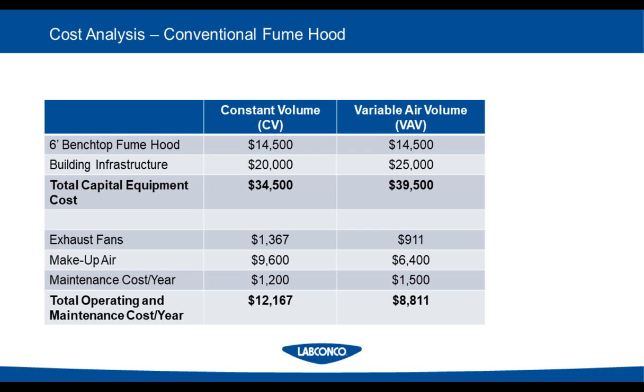And again, drawing attention to the makeup air portion of this table, it only requires about $6,400. And this number comes from taking a typical cost for fume hoods of about $8 per CFM per year. And that's where we're getting these makeup air numbers. And the VAV overall has an operating and maintenance cost per year of $8,811. So there are significant yearly cost savings by going to a variable air volume system.